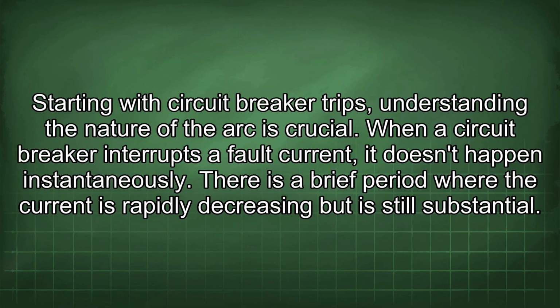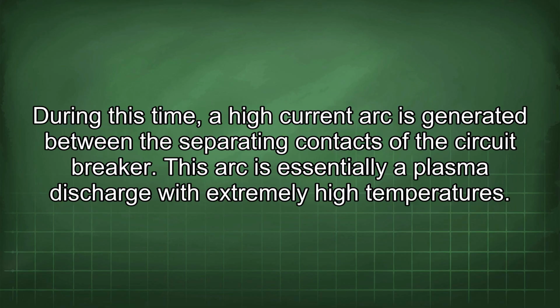Starting with circuit breaker trips, understanding the nature of the arc is crucial. When a circuit breaker interrupts a fault current, it doesn't happen instantaneously. There is a brief period where the current is rapidly decreasing, but is still substantial. During this time, a high current arc is generated between the separating contacts of the circuit breaker. This arc is essentially a plasma discharge with extremely high temperatures.